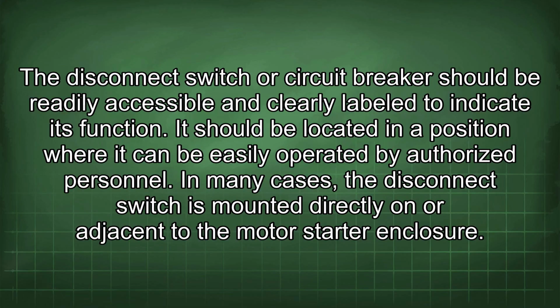The disconnect switch or circuit breaker should be readily accessible and clearly labeled to indicate its function. It should be located in a position where it can be easily operated by authorized personnel. In many cases, the disconnect switch is mounted directly on or adjacent to the motor starter enclosure.